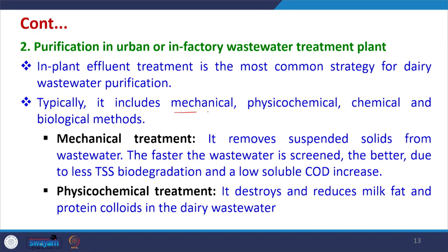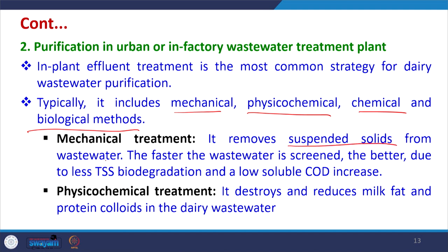In-plant effluent treatment is the most common strategy for dairy wastewater purification, typically including mechanical, physicochemical, chemical, and biological methods. Mechanical treatment removes suspended solids from wastewater; the faster the wastewater is screened the better, due to less TSS biodegradation and low soluble COD increase.